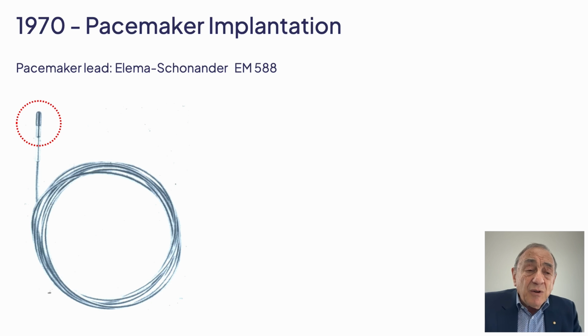The electrode was approximately 25 to 50 millimetres squared, was shiny stainless steel, and it was felt that the larger the electrode, the more likely it was going to make contact with the endocardium and therefore pace the heart. This, however, resulted in a low impedance lead which drained the power source.